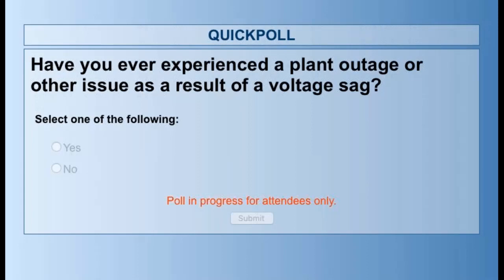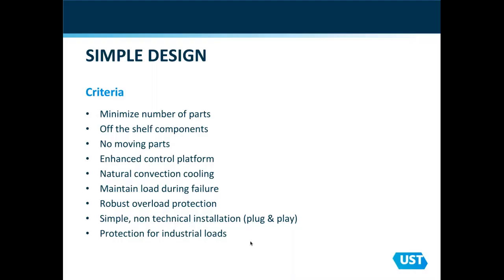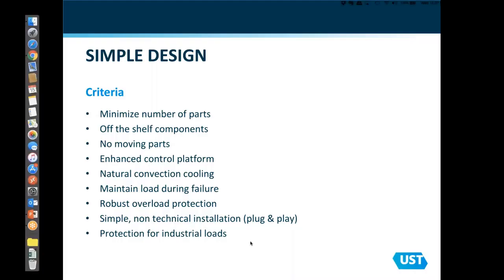We have a very simple design. We use a minimal number of parts. All of our components are typically off-the-shelf, so they're easy to replace if needed. Our base design has no moving parts, so it's highly reliable. We use natural convection for cooling in our NEMA 1 enclosures. We can maintain the load during any type of failure with a bypass arrangement.